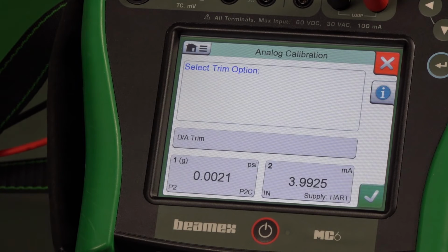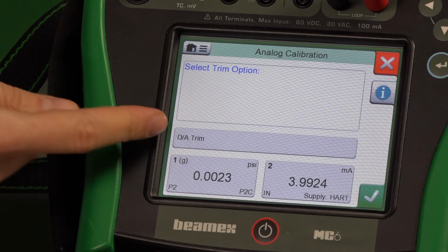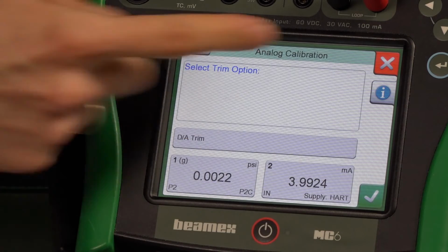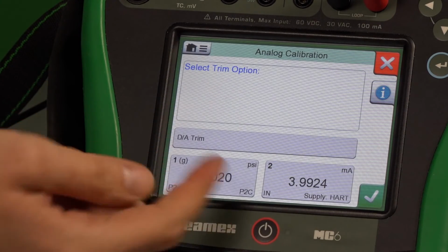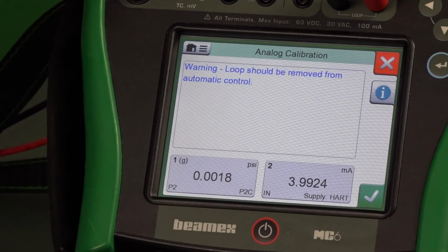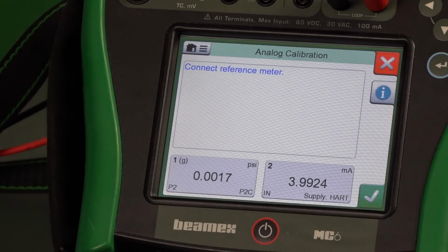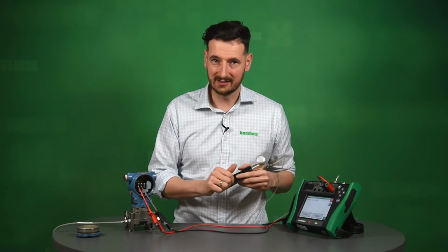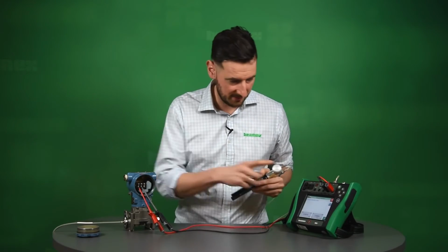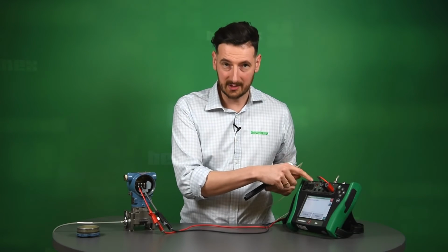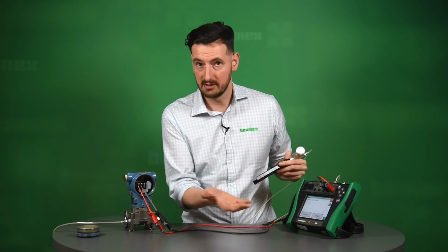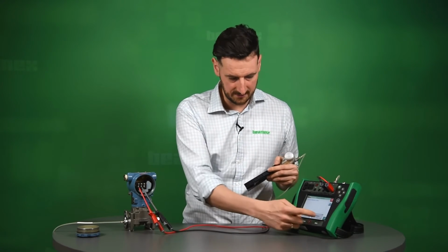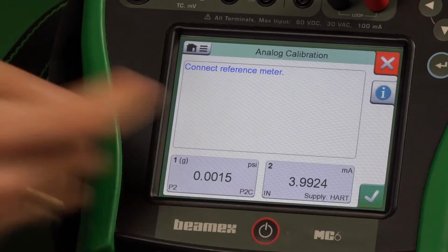And again, the guidance is going to be within your Hart transmitter. So it's going to be here, and it's saying to you, select option. We only have the digital to analog trim. You click OK. It's asking you to remove from automatic control. It's fine. It's asking you to connect a reference meter to this. We don't have to do that because our calibrator is already measuring 4 to 20 milliamps, it has that built in inside. So we just click OK.